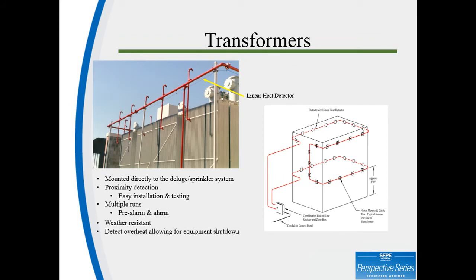Another very popular application for digital linear heat detection within the power gen industry is transformers. The digital linear heat detector can be placed directly on the transformer using specific attachment devices to allow for installations without drilling into the transformer. An important note, though, with this type of installation style is that you should not fully encircle the transformer. If you look at the illustration on the right side of your screen, you will see the detector almost encircles the transformer and then returns back to the start. The purpose behind not completely encircling the transformer is to limit EMI and RFI interference.